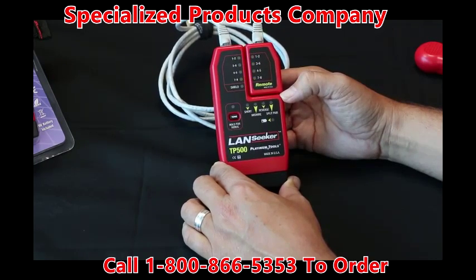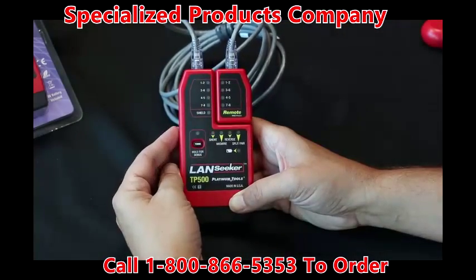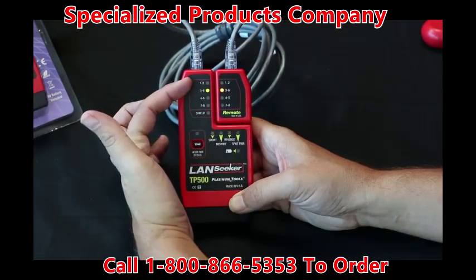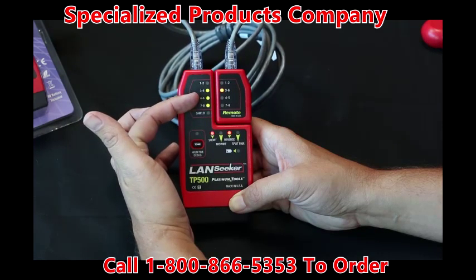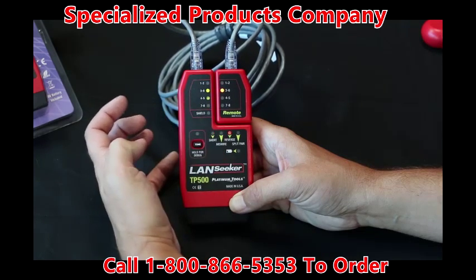Now let's see a bad cable. Let's try this next cable on the LANSeeker. Connect it into the remote. Right away we're seeing there is an open on one and two. Looks like three and six are good. And there's a fault on four and five and seven and eight. And there's a short and a reversal.